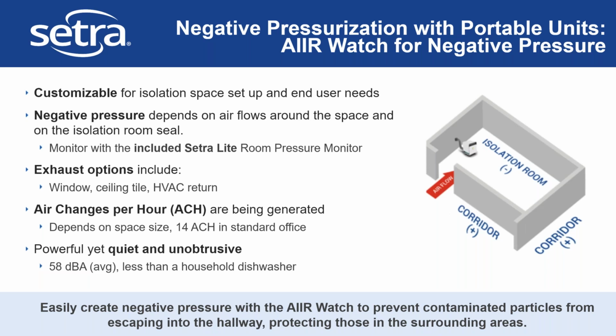The portable unit, the Setra AIIR Watch, is what actually does the work to pull air out of the space. You can set up an exhaust that goes out a standard window, up into a ceiling tile, or incorporated into your HVAC return. This pulls the air out and sends it away to create negative pressure relative to the hallway, the concept we discussed at the beginning. It generates air changes per hour depending on your space size—we have a calculator for that—but in the standard sized office we used for testing during our design, it generates 14 air changes per hour.